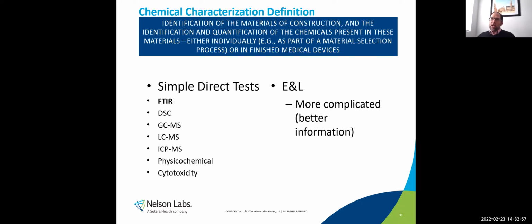Extractables are chemicals that come off under exhaustive or elevated extraction conditions, like higher temperatures and more aggressive solvents. Leachables are chemistry that comes off under normal use conditions, like body temperature for 4 hours or whatever. But you get a lot more information in extractable and leachable testing.